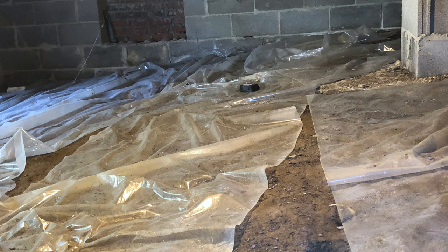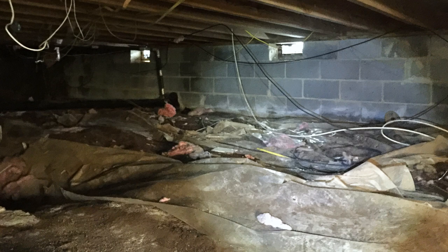That being said, it's not very effective. Imagine that you have a vapor barrier — I'm going to show you some pictures here of some different vapor barrier installations. You put down a piece of plastic and they don't overlap and tape the plastic, they just butt up the edges. Then the first knee that hits that plastic makes a gap where all of that ground is exposed and moisture comes up out of the ground into the crawl space. The word is vapor barrier, but vapor retarder is probably a better way to describe it. What plastic is designed to do is to keep the moisture from evaporating quickly out of the ground so it doesn't get absorbed by your wood and cause mold problems in the future.